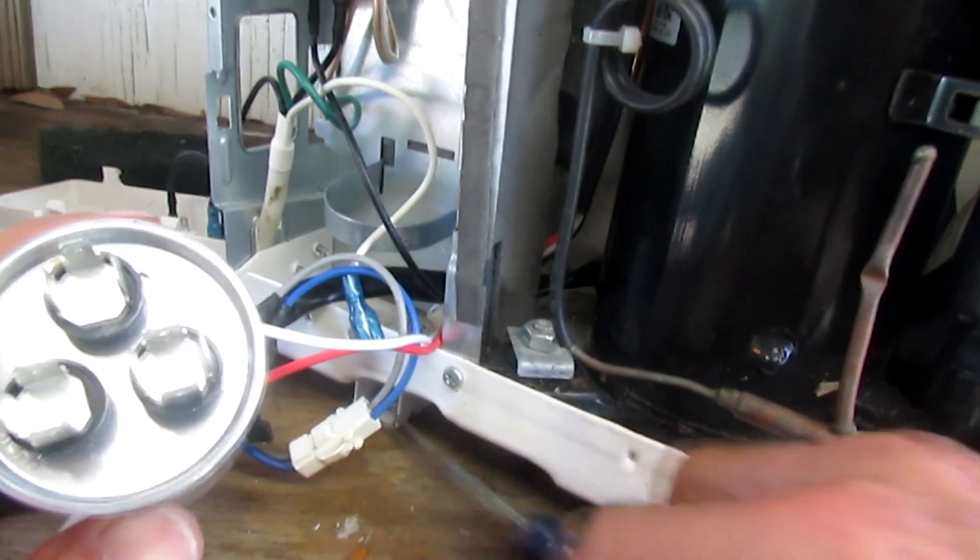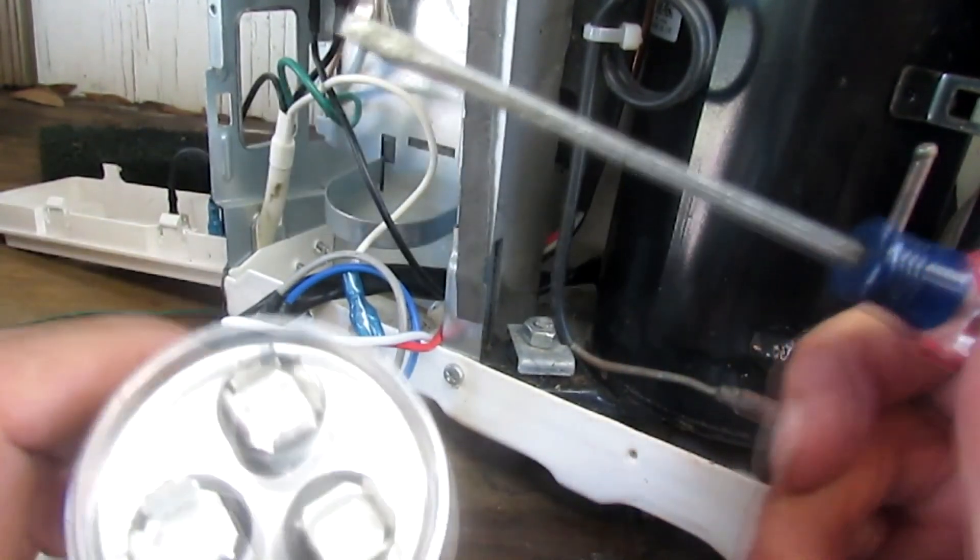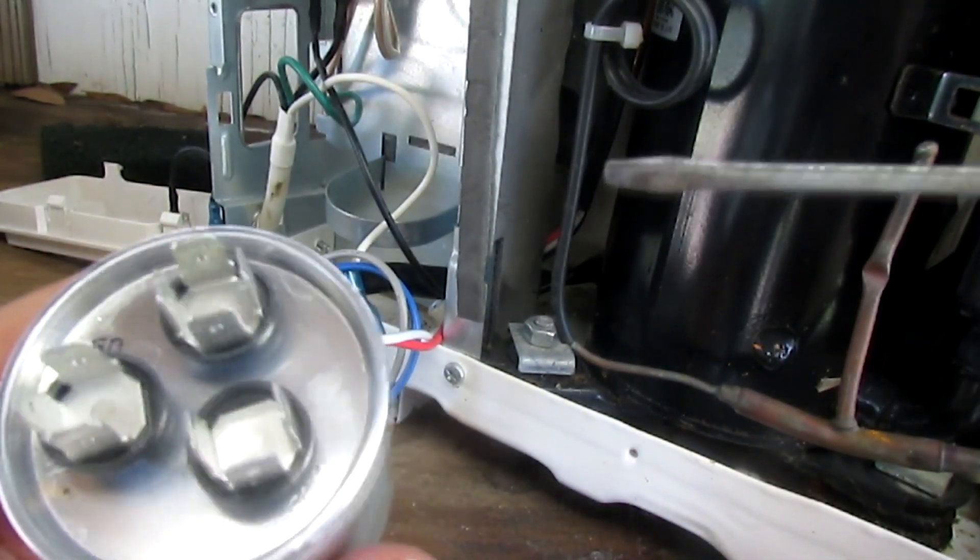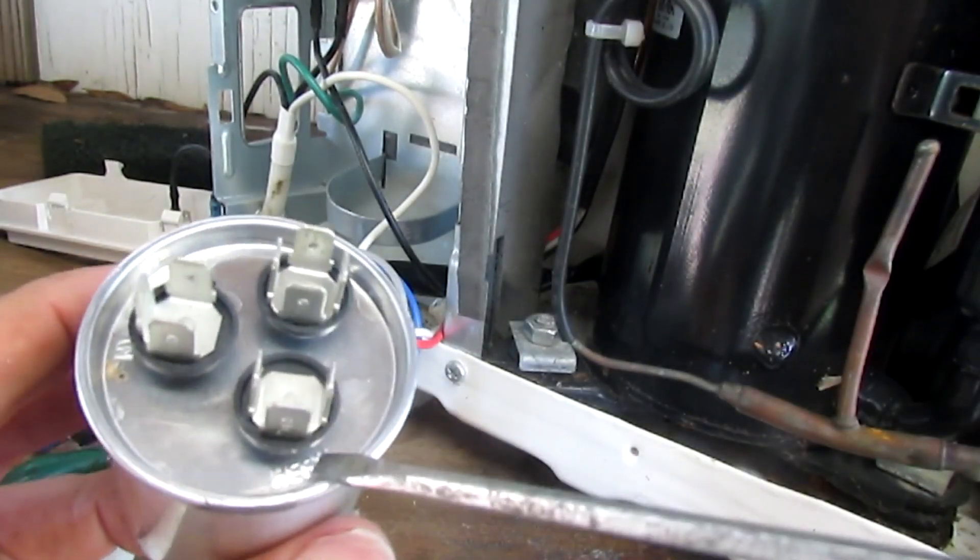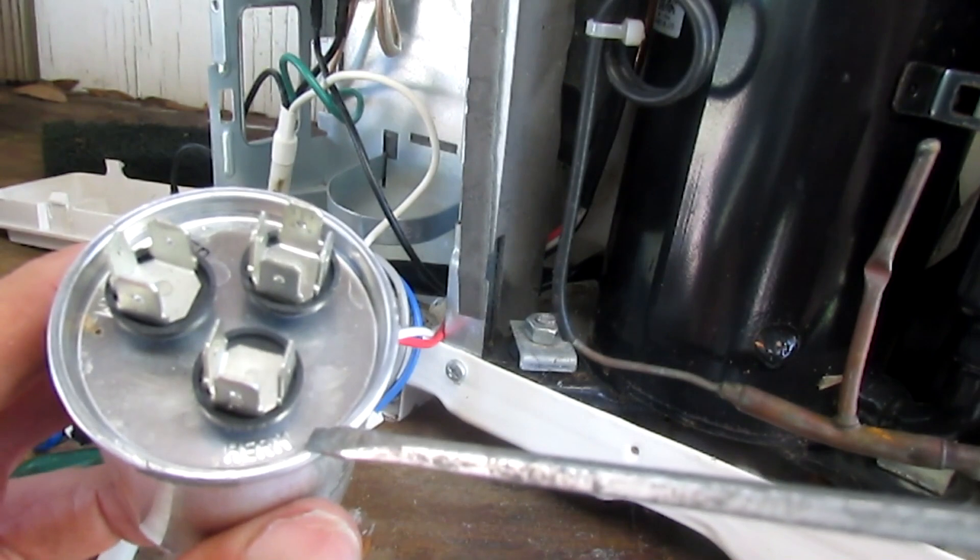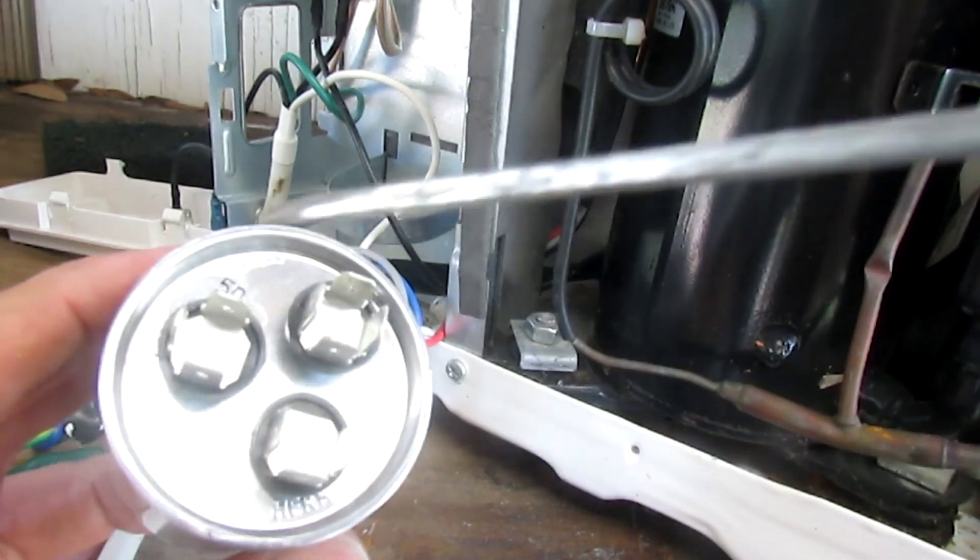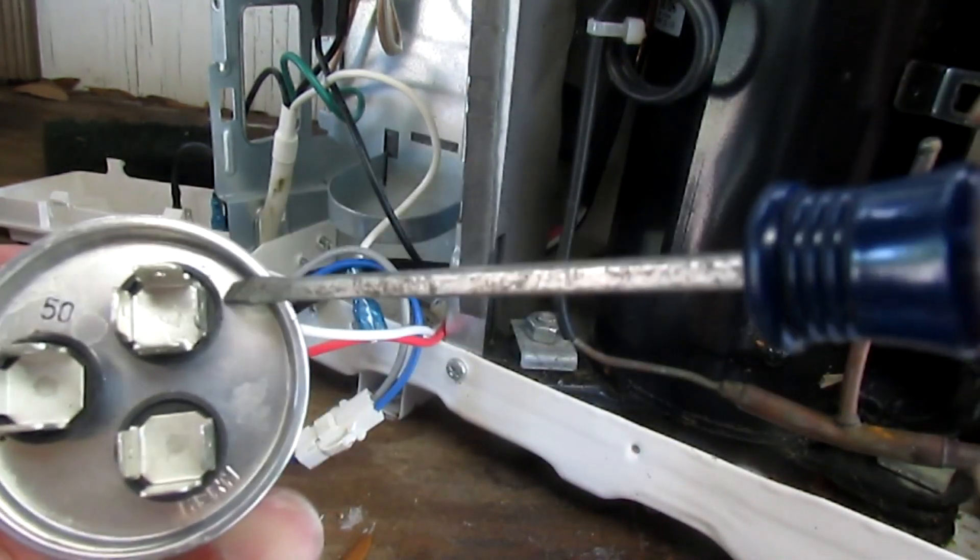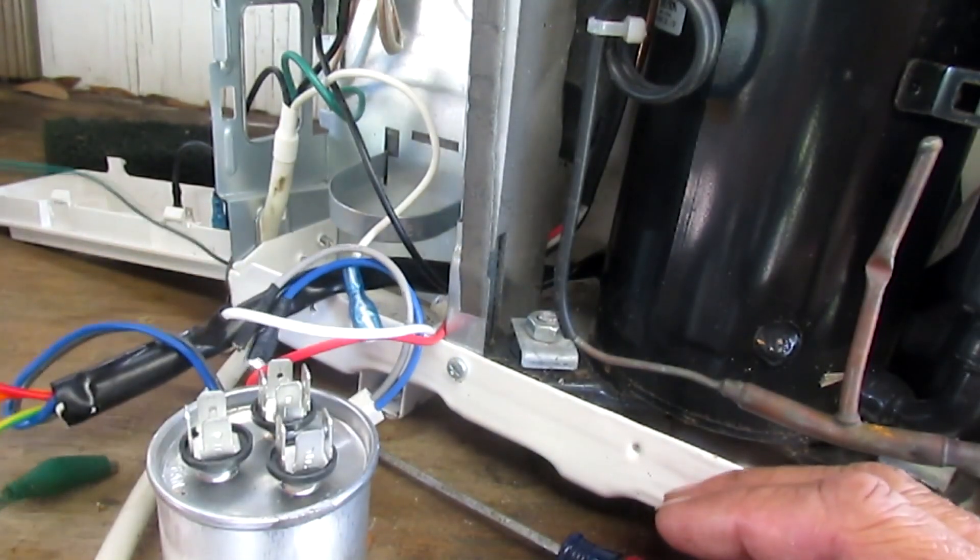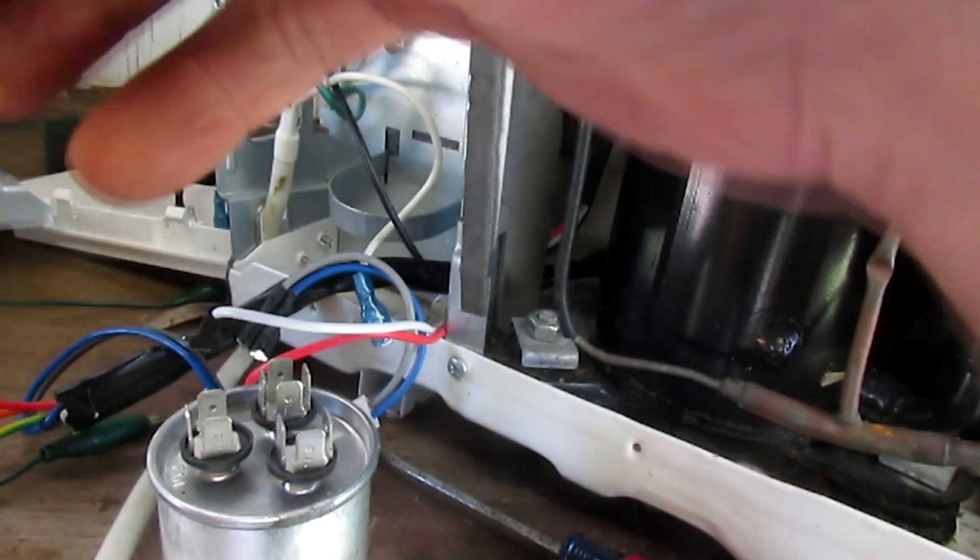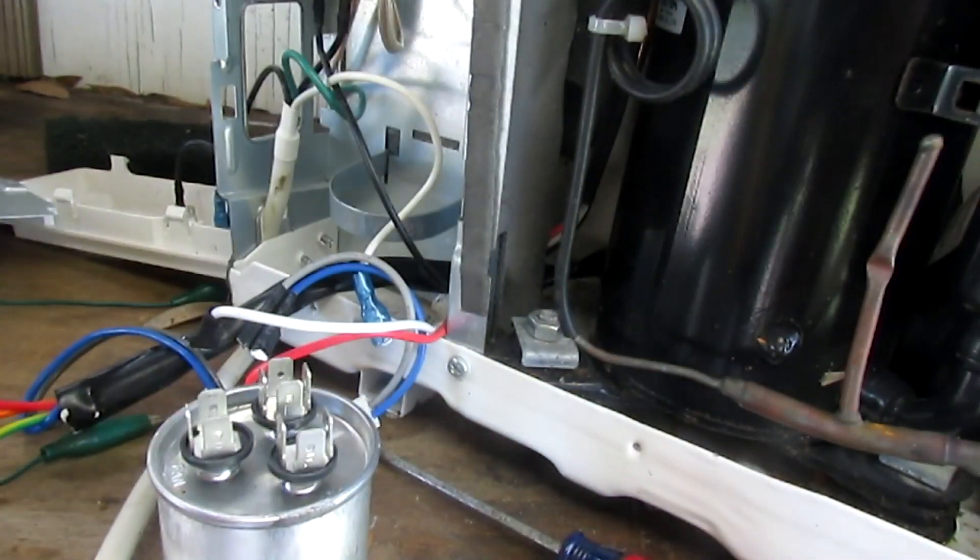Now I'm looking at this, and you can see on these dual capacitors they're labeled. One contact here says Herm. On the other contact, it says fan, and then here you see I have a little C for common. Now make sure you get them all shorted out so you don't get shocked.